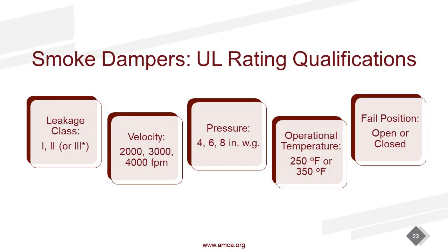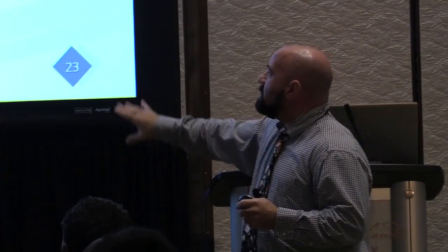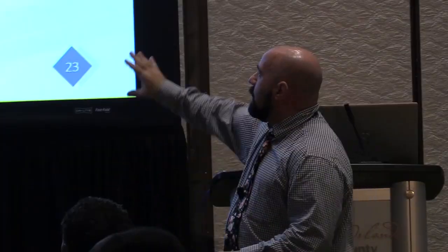We told you that smoke dampers are a dynamic condition. Velocity and pressure ratings, we need to know what those are as well. The operational temperature. This kind of misleads folks. Smoke dampers are not tested under fire conditions. They control the movement of smoke. That operational temperature refers to the actuator. The actuator will have a 250 or 350 rating.